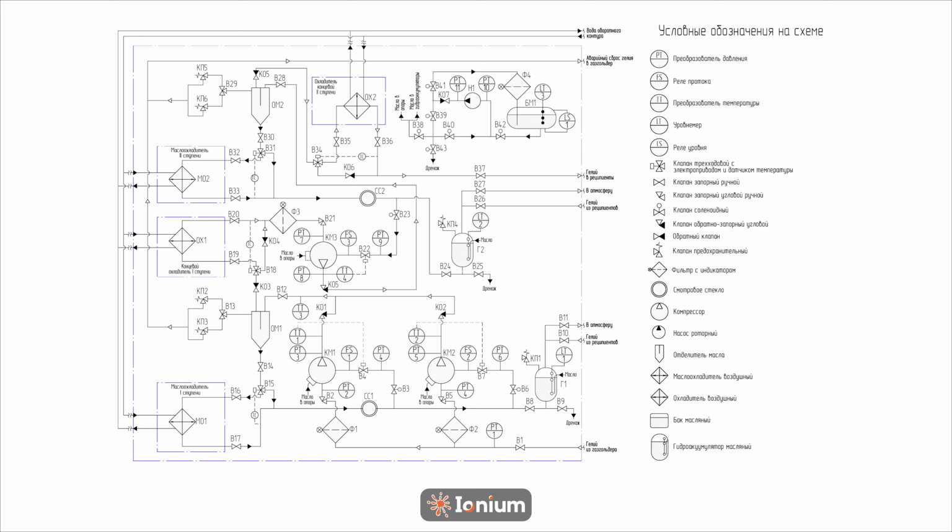To boost the efficiency of the compression process and lower the operating temperatures of compressor parts, screws, suspensions, seals, etc., oil is injected at a position 2/3 along the screw axis from the suction port, cooled to about 28 degrees Celsius by a water oil heat exchanger, position MO1, with a flow rate of about 36 cubic meters per hour at compression pressure, resulting in minimal hydraulic losses at the oil separator, position OM1, and the cooler, position MO1, approximately 5.2 bar absolute.